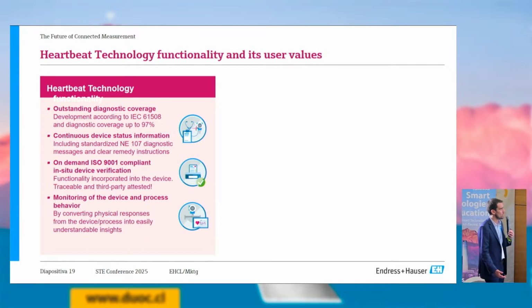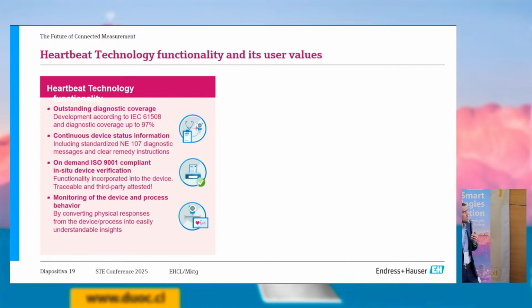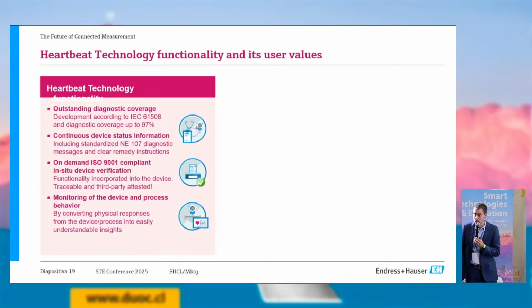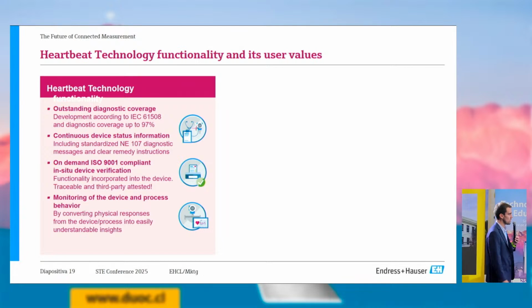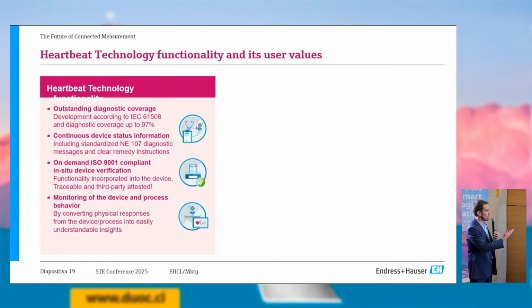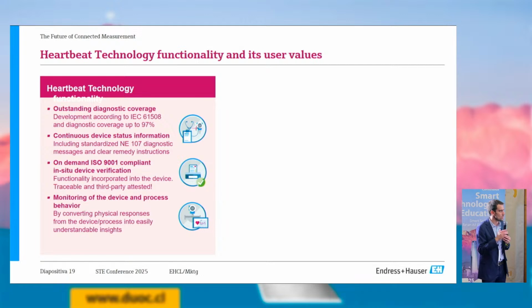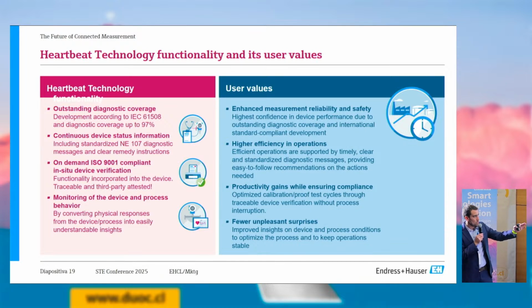Continuous device status information according to the standardized NAMUR NE107 diagnostic message, with interactive symbols, can show you the root cause of a failure along with the code and a possible solution to fix it. There's also on-demand ISO 9001 compliant in-situ device verification and monitoring, which I'll show you in a couple more slides. This enhances measurement reliability, higher efficiency in operations, and translates into more benefits for the customer.